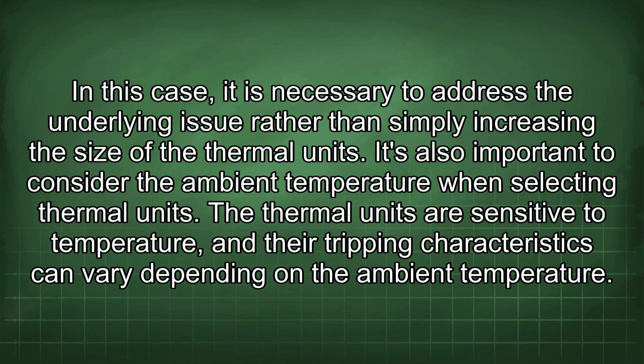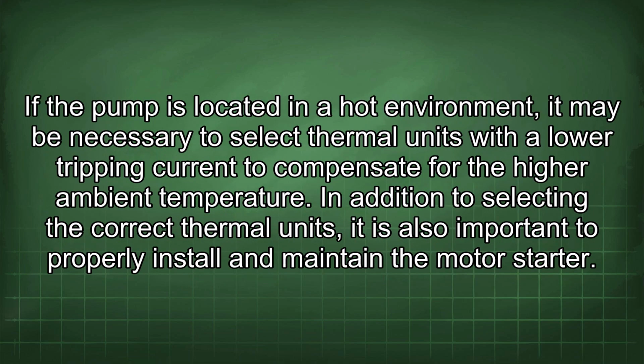In this case, it is necessary to address the underlying issue rather than simply increasing the size of the thermal units. It's also important to consider the ambient temperature when selecting thermal units. The thermal units are sensitive to temperature, and their tripping characteristics can vary depending on ambient temperature. If the pump is located in a hot environment, it may be necessary to select thermal units with a lower tripping current to compensate for the higher ambient temperature.